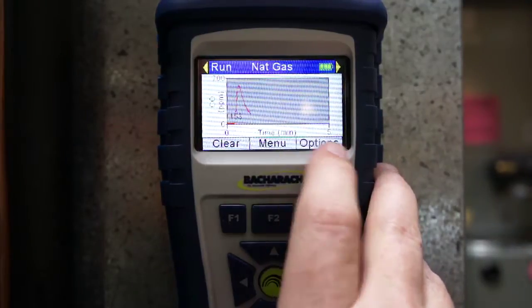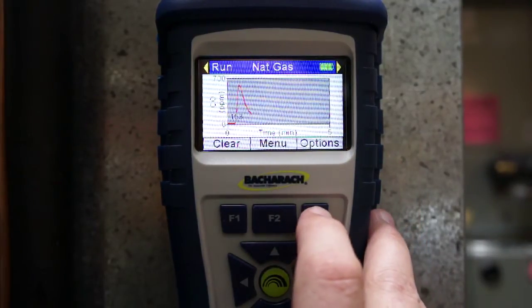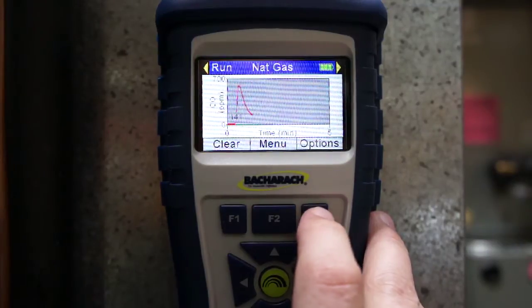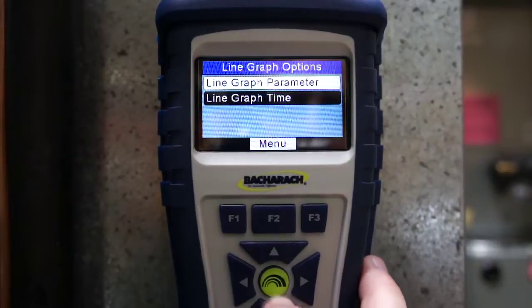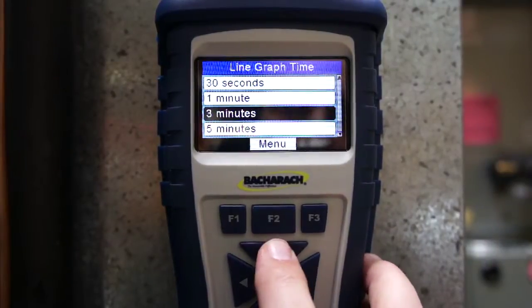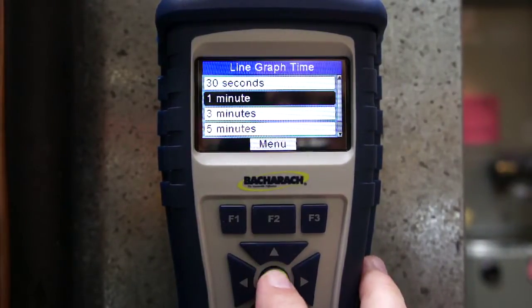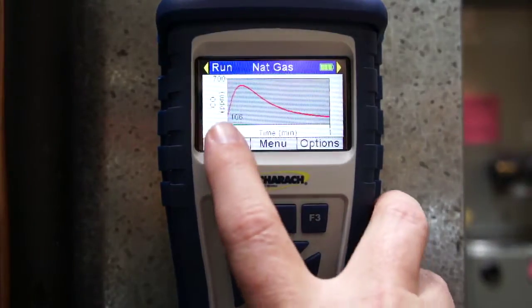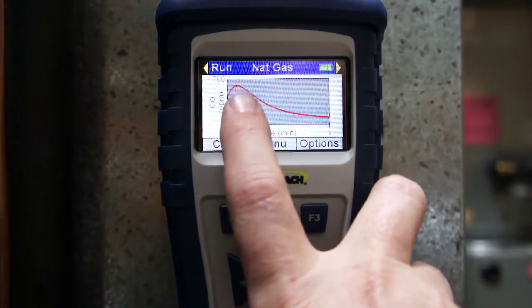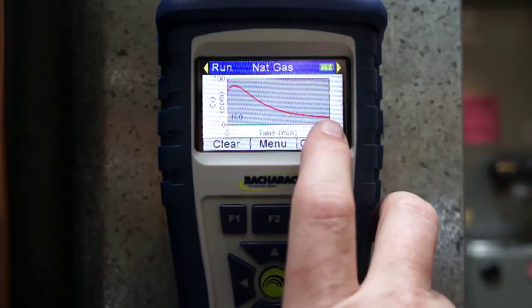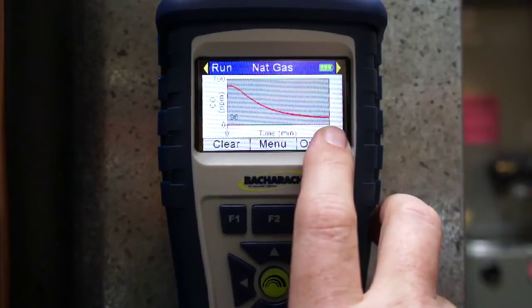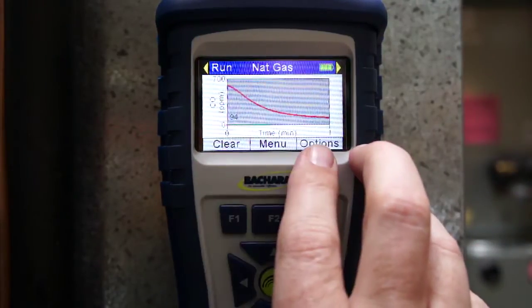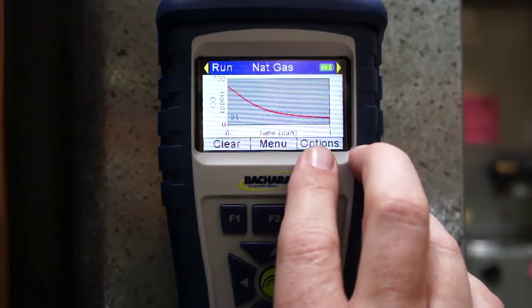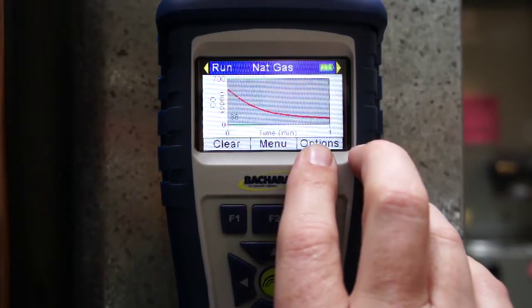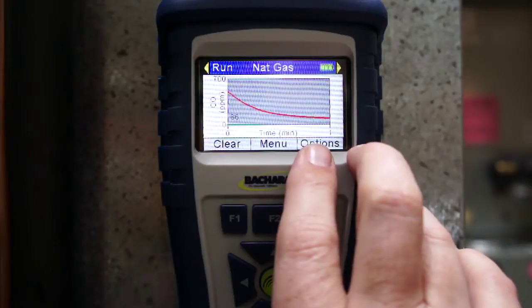And so now maybe I want to change that so it doesn't quite look so sharp, or so I can get a little bit better idea what the readings were. I can hit the options key here, scroll down to line graph time, change that to maybe a minute because we haven't been running that long, hit enter, and now I can get a better idea here. We're close to 600 ppm of CO when it started, and we're definitely trending in a downward position. Now I can take any single parameter that I want to trend, whether it's O2, CO, CO air free, whatever I want to trend, and I can trend it on this bar graph.